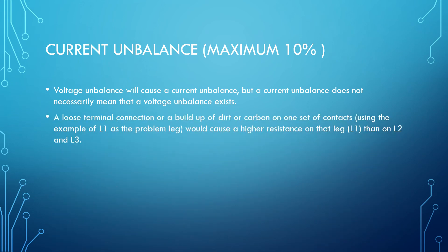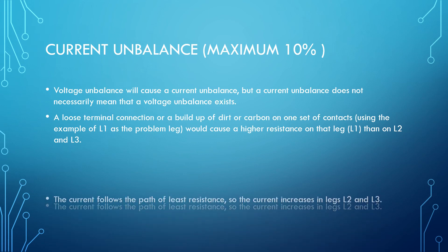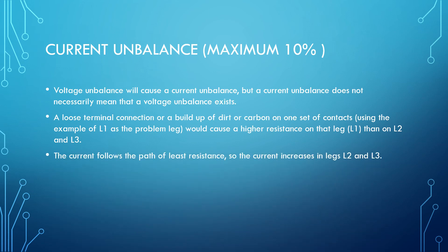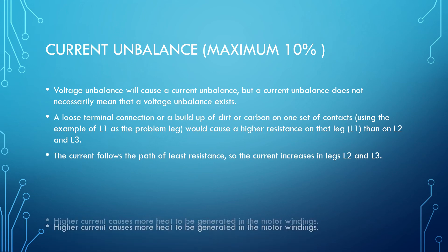A loose terminal connection or a buildup of dirt or carbon on one set of contacts — using the example of L1 as the problem leg — would cause a higher resistance on that leg, L1, than on L2 and L3. The current follows the path of least resistance, so the current increases in legs L2 and L3.